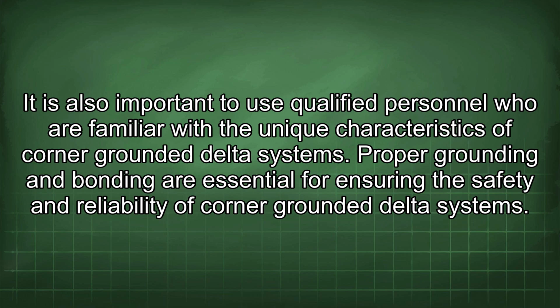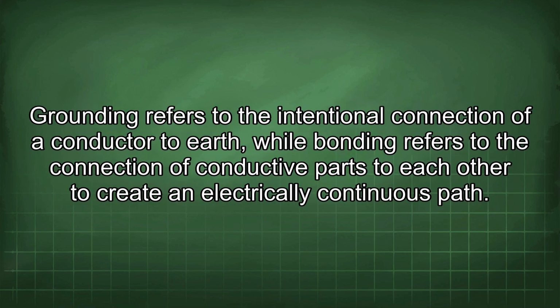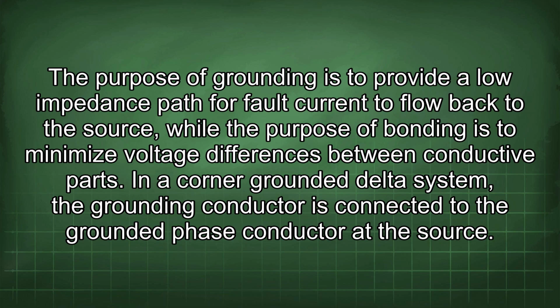Proper grounding and bonding are essential for ensuring the safety and reliability of corner-grounded delta systems. Grounding refers to the intentional connection of a conductor to earth, while bonding refers to the connection of conductive parts to each other to create an electrically continuous path. The purpose of grounding is to provide a low impedance path for fault current to flow back to the source, while the purpose of bonding is to minimize voltage differences between conductive parts.